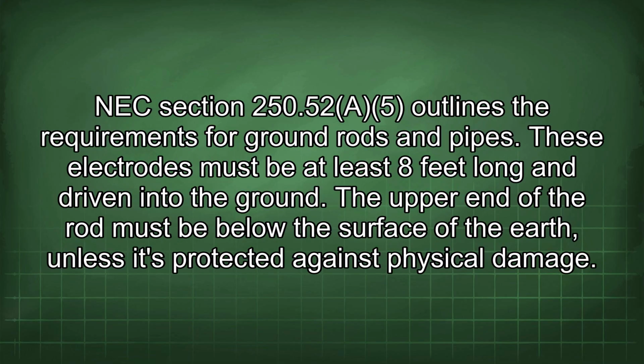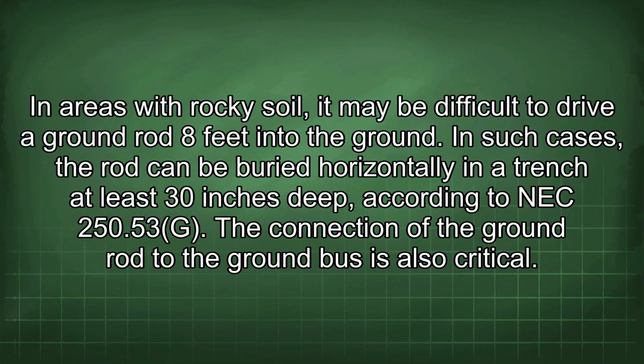NEC Section 250.52 outlines the requirements for ground rods and pipes. These electrodes must be at least 8 feet long and driven into the ground. The upper end of the rod must be below the surface of the earth unless it's protected against physical damage. In areas with rocky soil, it may be difficult to drive a ground rod 8 feet into the ground. In such cases, the rod can be buried horizontally in a trench at least 30 inches deep according to NEC 250.53(G). The connection of the ground rod to the ground bus is also critical.